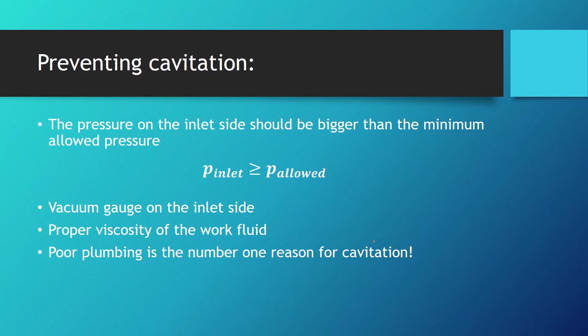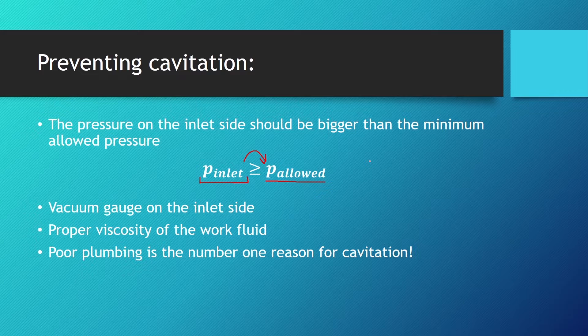How can we prevent cavitation? The pressure on the inlet side should be greater than the minimum allowed pressure — that is, the pressure below which vapor bubbles begin to form. We can put a vacuum gauge on the inlet side, ensure the work fluid is operating at the proper viscosity, and do a good job of designing the plumbing system of our hydraulic system.